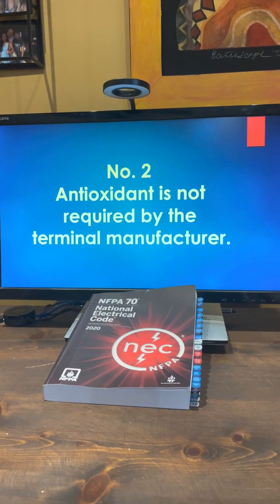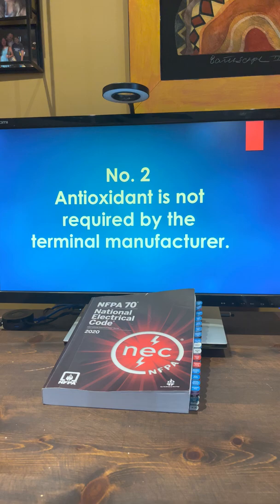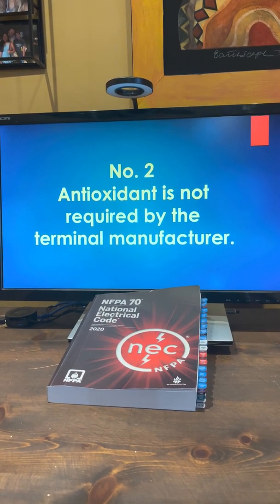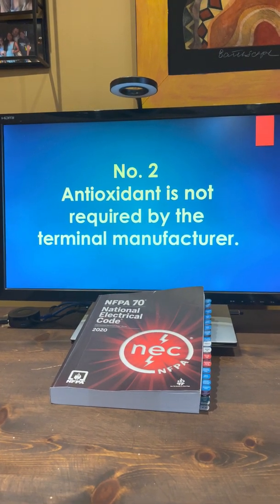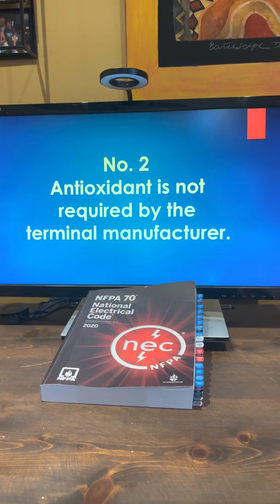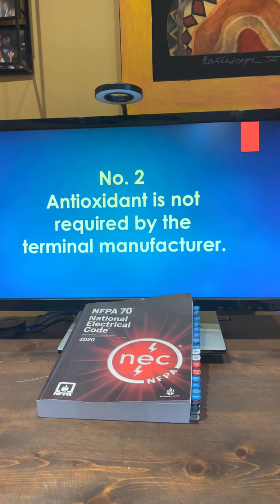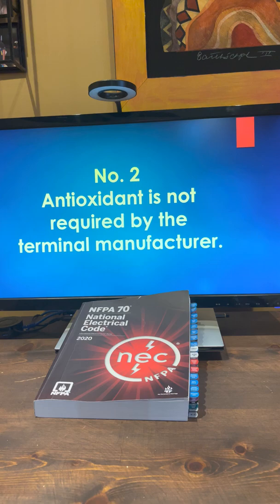Number two: antioxidant is not required by the terminal manufacturer. Burndy or Ilsco — they do not say that you have to use an antioxidant when you're terminating aluminum wire. You can buy terminals that actually have the antioxidant paste inside the terminals, like compression ones, but it's not required.